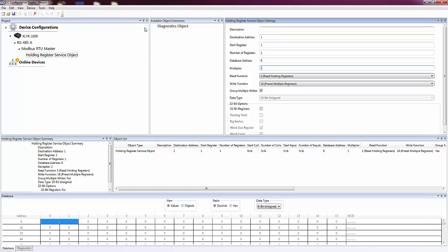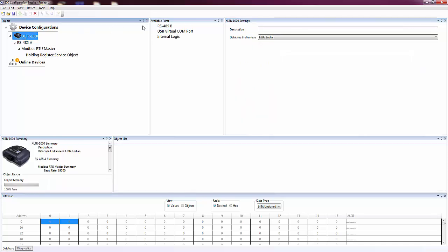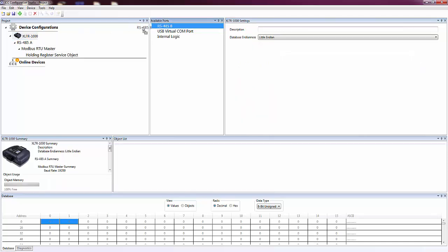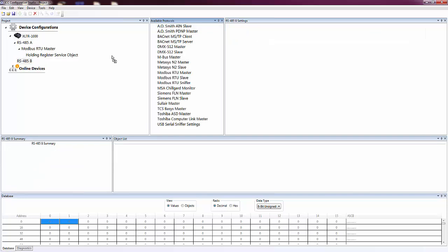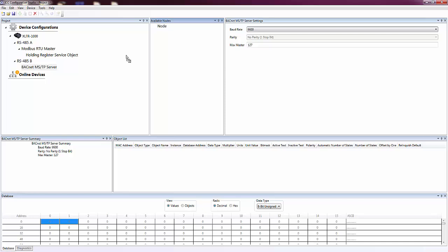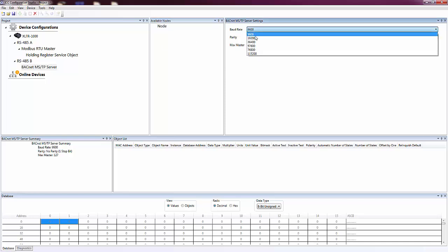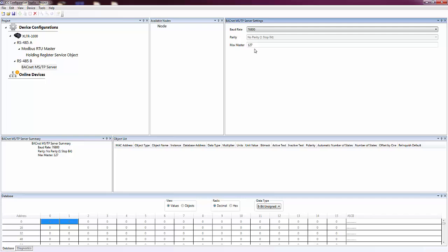Now that we're done configuring the gateway to access data from a device, we now need to expose the data onto a different network. We'll configure the other port for BACnet MSTP server and set the baud rate settings to match our BACnet network.